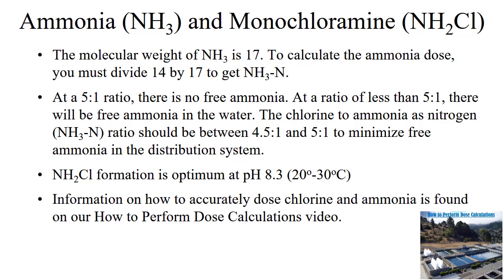At a 5-to-1 ratio, the ammonia added to the water will combine with hypochlorous acid, and the free ammonia concentration is 0. If the ratio is less than 5-to-1, there will be some free ammonia in the water. The chlorine-to-ammonia-as-nitrogen ratio should be between 4.5-to-1 and 5-to-1 to minimize free ammonia in the distribution system. Excessive free ammonia can cause nitrification and negatively affect water quality. The optimum conditions for forming monochloramine are a pH of 8.3 and a water temperature between 20 and 30 degrees Celsius. If you are interested in more information on how to calculate the proper dose and feed rates of chlorine and ammonia, please watch our How to Perform Dose Calculations video.